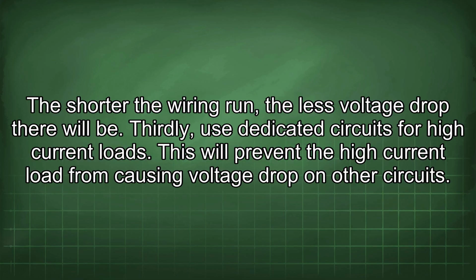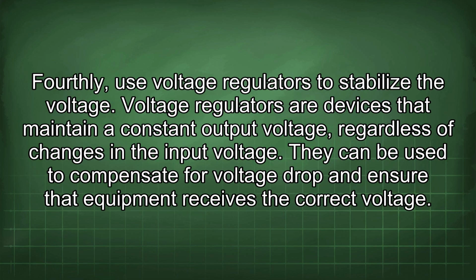Thirdly, use dedicated circuits for high current loads. This will prevent the high current load from causing voltage drop on other circuits. Fourthly, use voltage regulators to stabilize the voltage. Voltage regulators are devices that maintain a constant output voltage regardless of changes in the input voltage. They can be used to compensate for voltage drop and ensure that equipment receives the correct voltage.